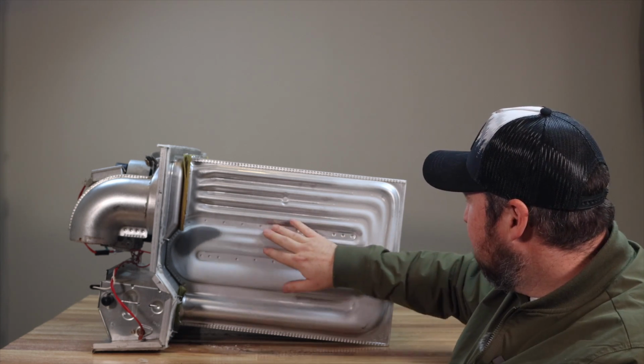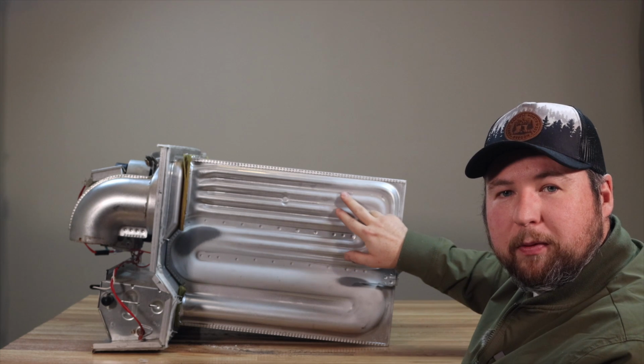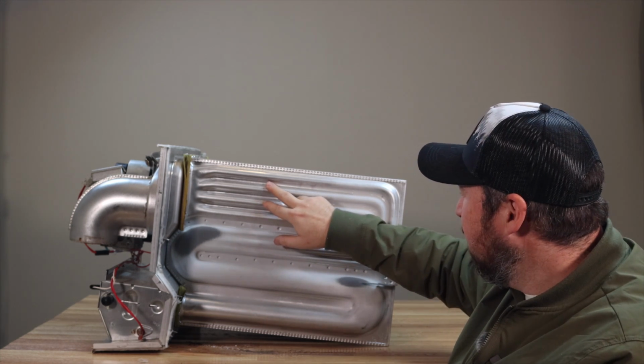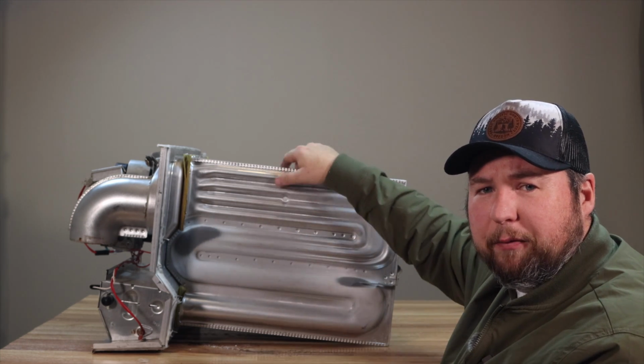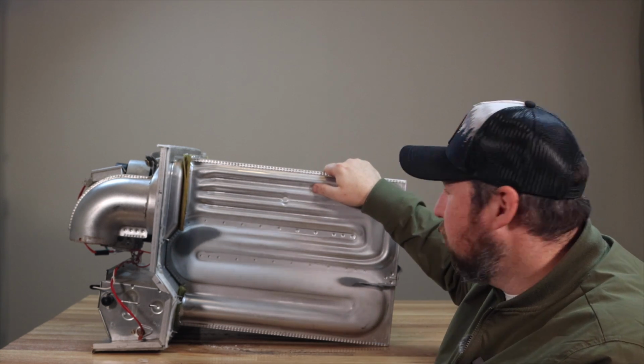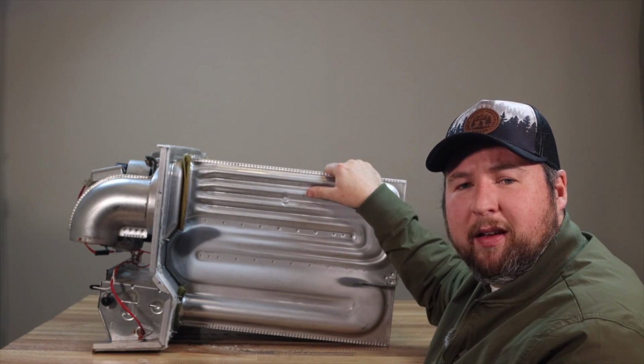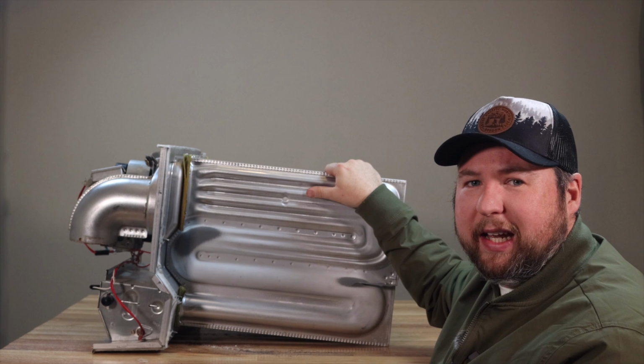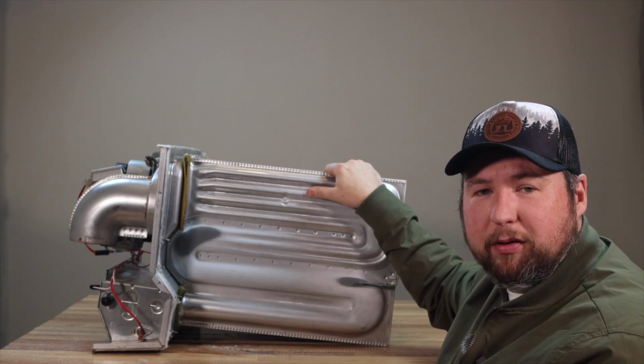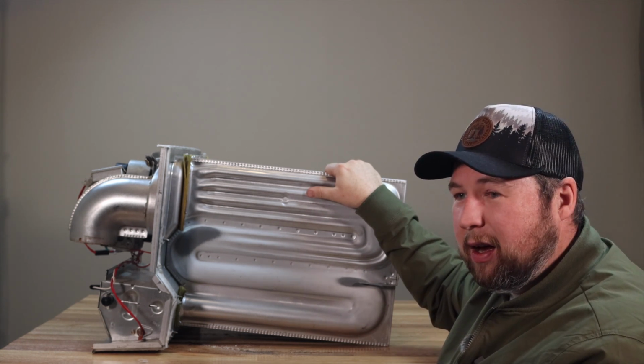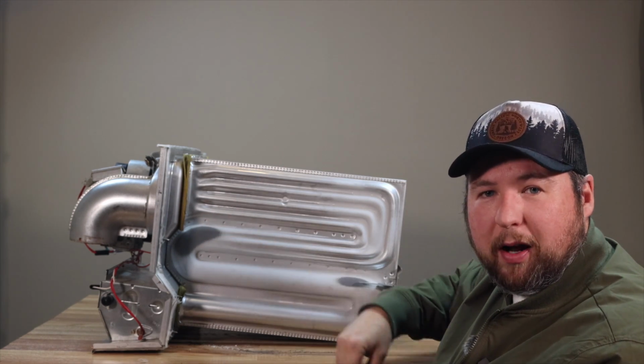So what they do is they basically squeeze into these smaller tubes, and that's just to maximize the heat transfer. And you'll see in 90% furnaces, this is something that they do to an extreme to really maximize, you know, they just want to suck up all that heat out of the heat exchanger just to maximize the total amount of heat that you're pulling from the combustion process.